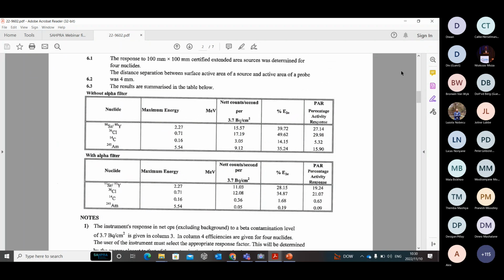Okay, thank you, Mr. Ditola. This is the table for without the alpha filter. The B20 comes with the alpha filter. You put it in front of the instrument. When we put it in front of the instrument, we calibrate the instrument, and these are the percentage activity responses, and all these are the values that you set inside the instrument through parameters, so that when you go to becquerel per square centimeter, it takes these parameter values in order to give you the reading in becquerel per square centimeter.